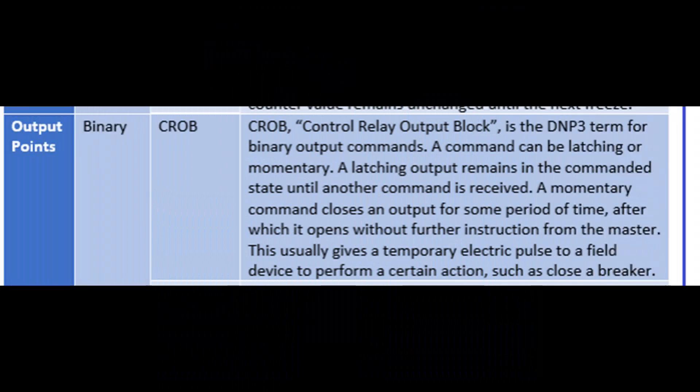The output point types for SCADA are binary and analog. Binary output points in DNP3 are called CROBs, which stands for Control Relay Output Block. A command to a CROB can be latching or momentary. A latching output remains in the commanded state until another command is received. A momentary command closes an output for some period of time, after which it opens without further instruction from the master — usually giving a temporary electrical pulse to a field device to perform an action such as closing a breaker.